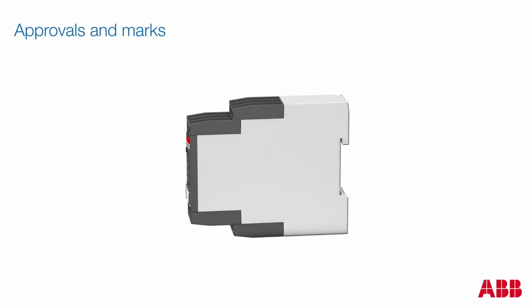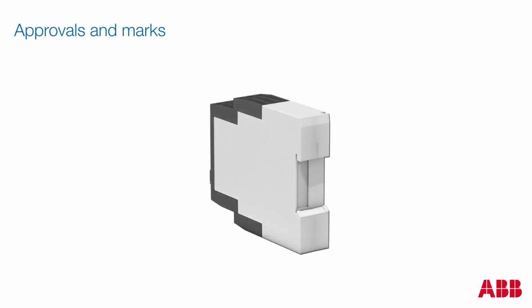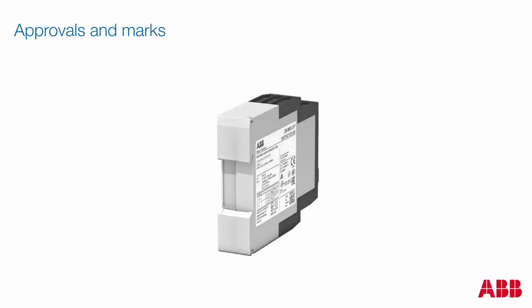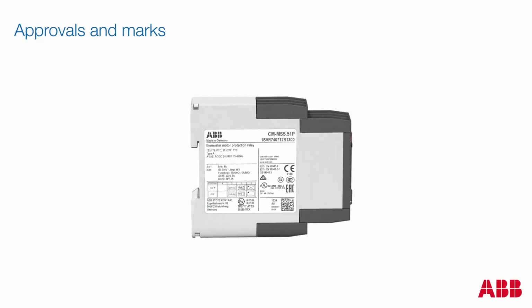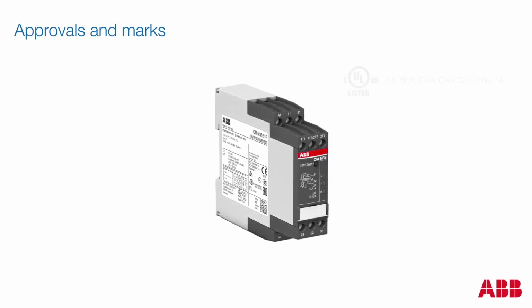The new thermistor motor protection relay CM-MSS covers many internationally valid approvals and markings, such as the UL 508 approval for the usage in the US market, as well as the CSA approval for the usage in Canada. The GL approval, which allows the monitoring of motors on ships or in many applications around the marine segment. The EAC certificate for being used in the Russian markets.